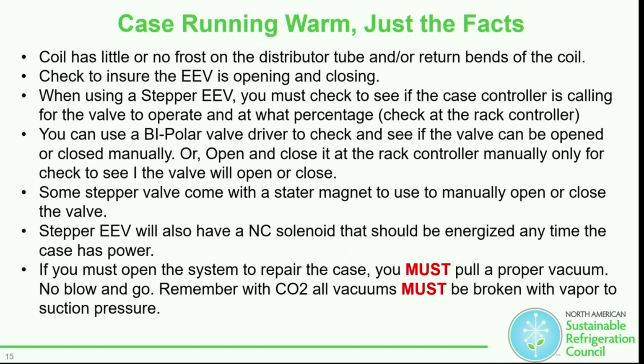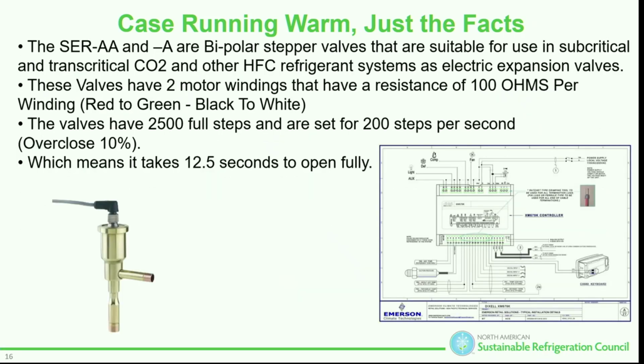If you must open up the system for repair, you must pull a proper vacuum, no blow and go. Remember, with CO2, all vacuums must be broken with vapor to suction pressure. Why is it so important that we not blow and go, besides it being illegal? What's going to happen if we have moisture in a CO2 system? Carbonic acid. We want to stay away from that. I don't want to change compressors. If you like changing compressors, it's up to you.